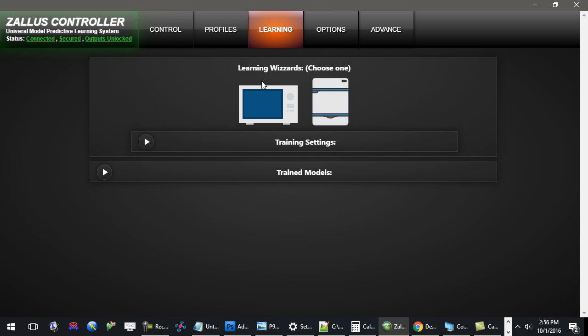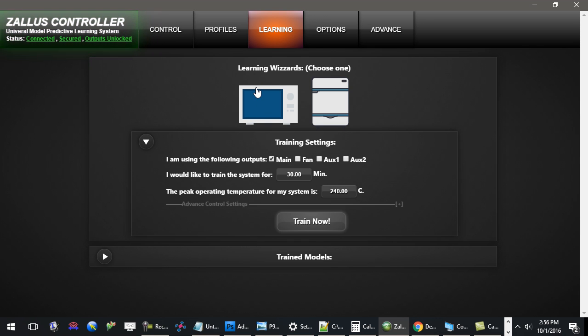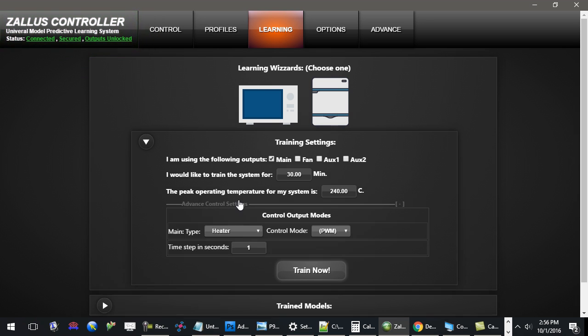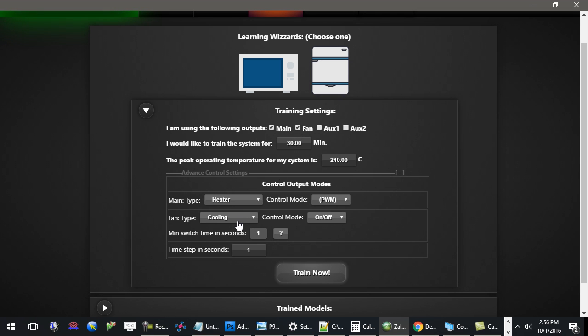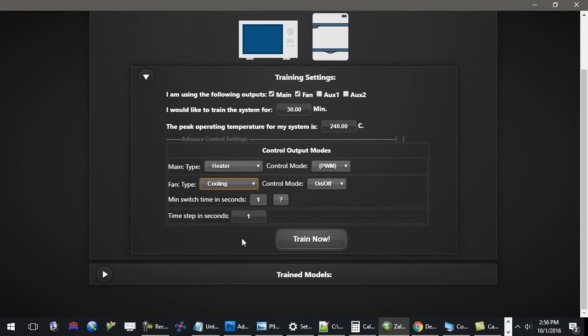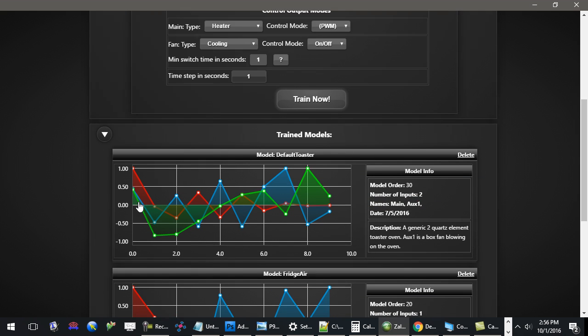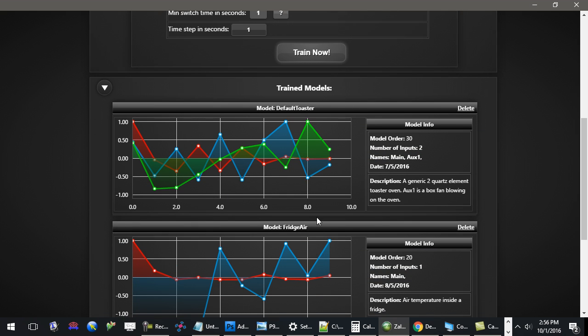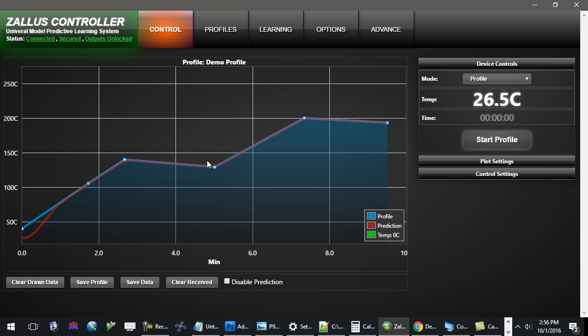How it learns and gets that mathematical model: when you buy the system, you'll first need to train it on whatever you're trying to control. I have some presets here, and you can also configure how many inputs and outputs you have and what exactly each of those do. When I hit Train Now, it will run through a training profile, and when it is done, it will give you a mathematical model that you can use to predict ahead of time how good of control you will be able to achieve.